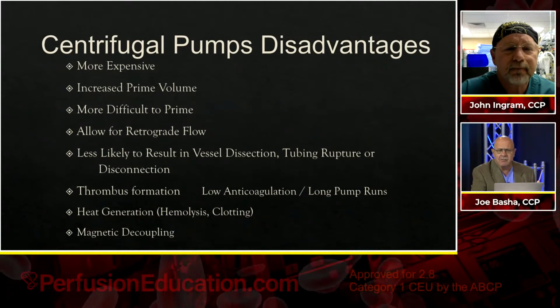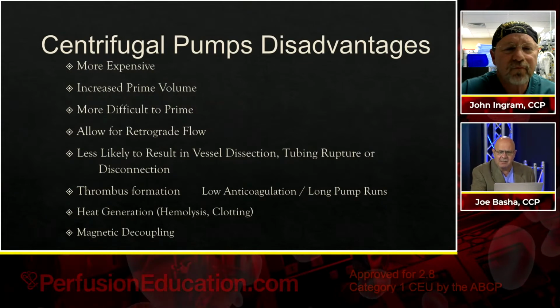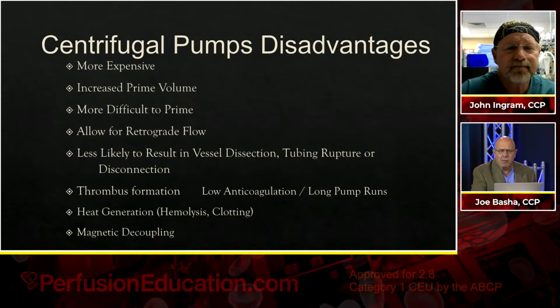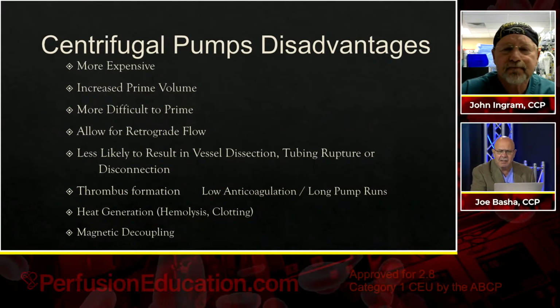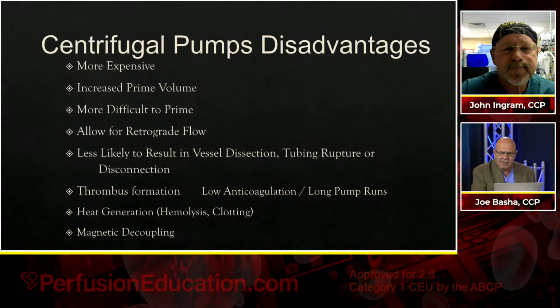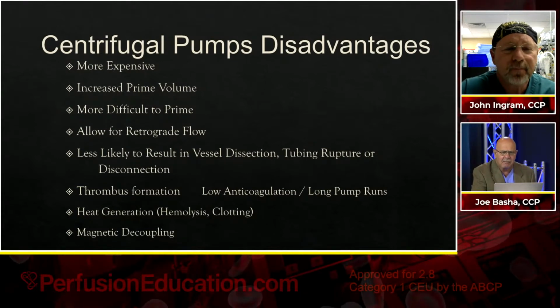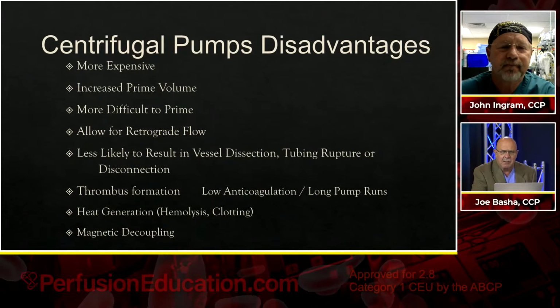Okay. So on the retrograde flow, there's been debate about having a one-way valve in the main arterial line to avoid that problem. It's the typical duckbill valve, which would work very effectively. But people are very hesitant to do that because if you did get air into your centrifugal cone, it's very easy to take it out, rotate it so that the outlet is facing straight up to your oxygenator, and then in a controlled fashion, open that line and let it reprime, and then put it back in and go back on pump and not have any problems with it.